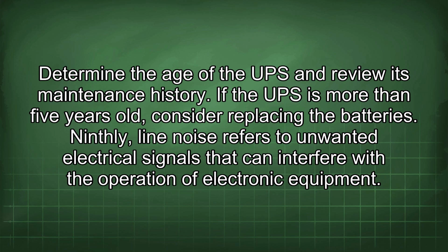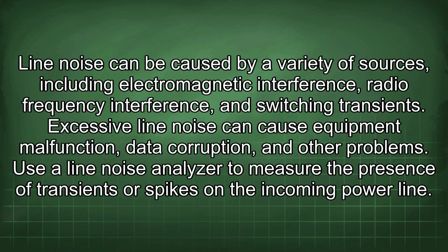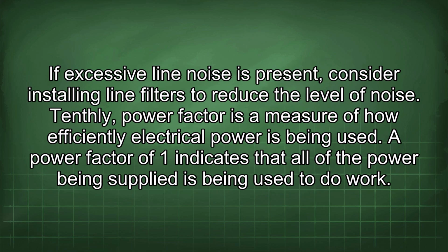Ninthly, line noise refers to unwanted electrical signals that can interfere with the operation of electronic equipment. Line noise can be caused by a variety of sources, including electromagnetic interference, radio frequency interference, and switching transients. Excessive line noise can cause equipment malfunction, data corruption, and other problems. Use a line noise analyzer to measure the presence of transients or spikes on the incoming power line. If excessive line noise is present, consider installing line filters to reduce the level of noise.